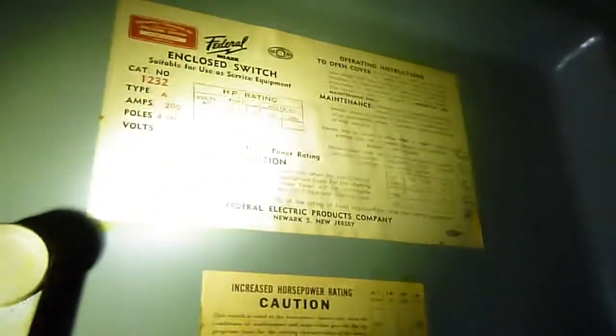These old Federal Pacific panels — in here, see the aluminum leads? The aluminum is okay on this. There should be antioxidant paste on that. This is telling us we've got a Type A, it's 200 amps, three-phase, four poles. The good thing about having three phase — this is commercial, you kind of expect it, and your bills are a little more manageable. There are sub-panels — two sub panels, and then this would make a third sub panel.